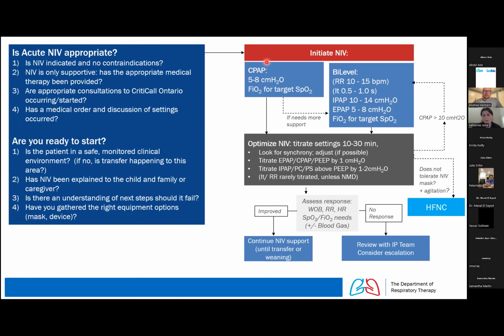If you're starting with CPAP, people always ask what do we start at? I would say 5 to 8 is a good starting point for anyone with a reasonable amount of distress, where you just need a bit of single level support. In terms of bi-level, depending on your device, you might have to set rates or I times, but certainly 10 on 5 as a starting point, and then augmenting. You could go up as high as 14, 16, 18 on that. I can correct the slide, it only says 14. And your EPAP, just like the CPAP, that's your baseline level. We would start that at 5 and augment to around 8, maybe even 10 if you're really pushing it for an adolescent.